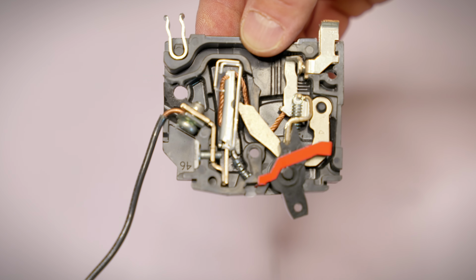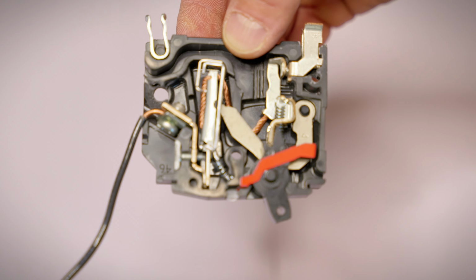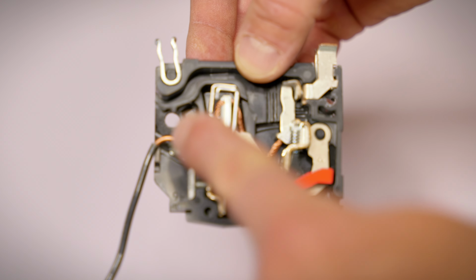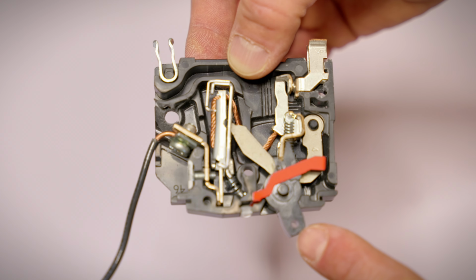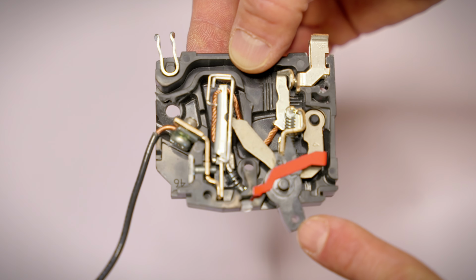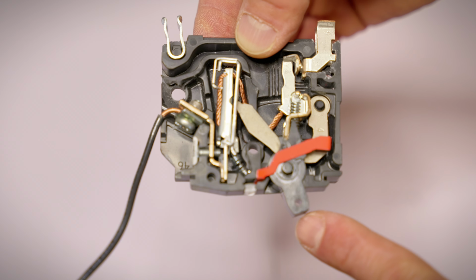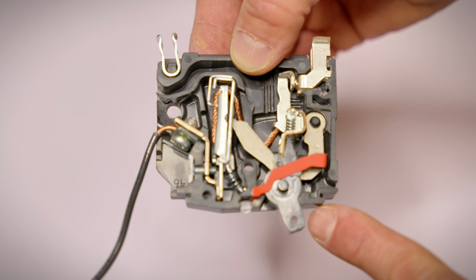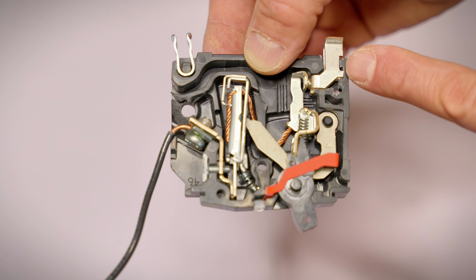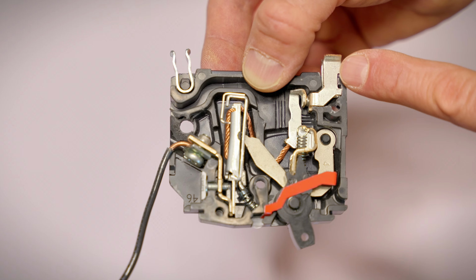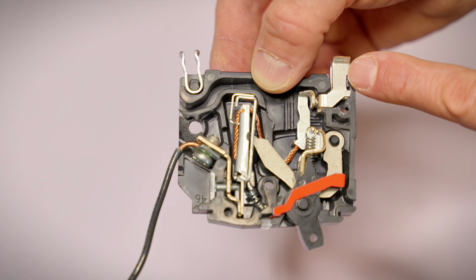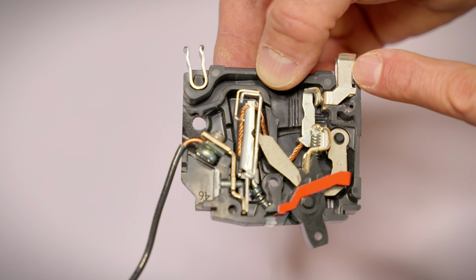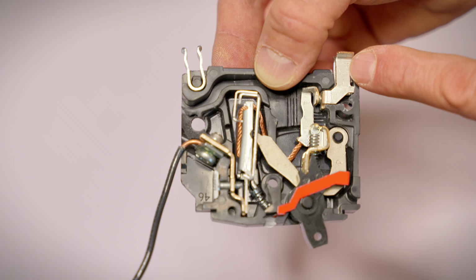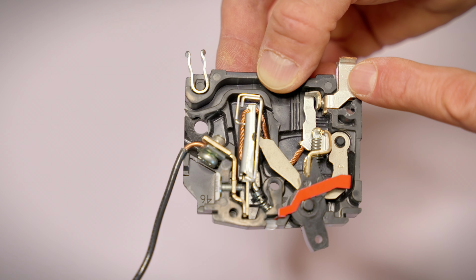Okay, as far as the internal components, we have, of course, the circuit path, as you can see. Of course, this is the switch. This is the mechanical piece that you move back and forth when you reset or turn on your circuit breaker. You have your non-moving terminal here. This is the one that actually hooks into the bus bar inside your circuit panel. It's getting its power from your main feed. So this is the input terminal into the circuit breaker.